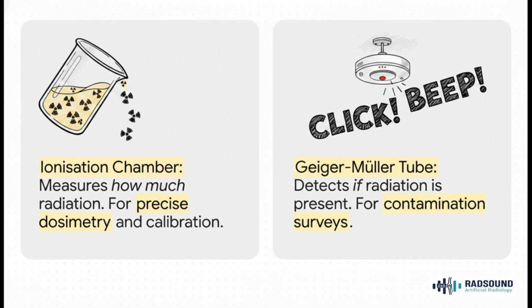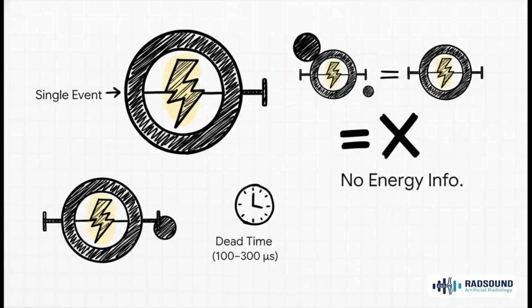A Geiger-Müller tube, on the other hand, that's your smoke alarm. It is brilliant at screaming, "Hey, there's radiation here," but it's absolutely terrible at telling you how much. One is for measurement, the other is for detection. Remember that super high voltage region on the curve? That's where the GM tube lives.